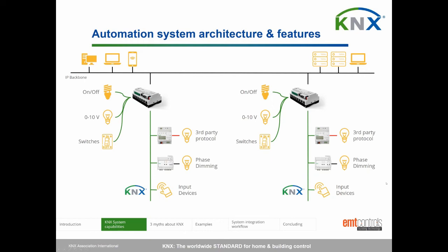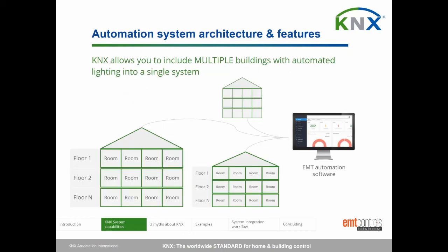Also, there are no tangible restrictions on the number of devices controlled by the network. Each KNX network provides the ability to gather more than 65,000 points at the same time. As we know, only electrical limitations of the bus may play a role in this maximum quantity of devices and subsystems.